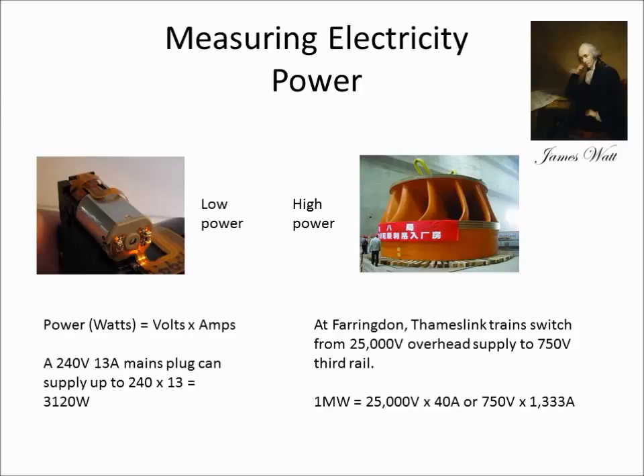I don't know quite how much power it takes to drive a train - let's say a megawatt, or perhaps a few megawatts. If you've got 25,000 volts, multiply that by 40 amps and you get 1,000,000 watts, so a megawatt. So 40 amps is not much more than you can get out of your domestic electricity socket at 13 amps - that's a relatively modest current because you've got a very high voltage.